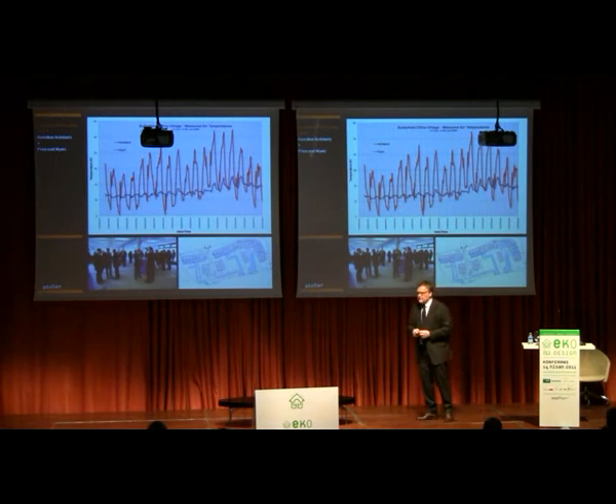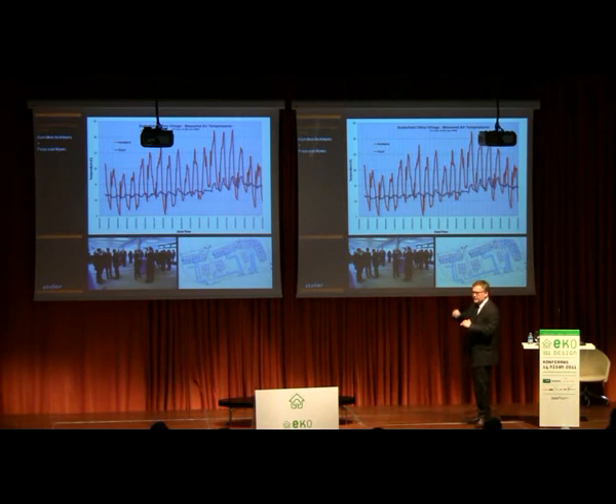In terms of thermal capacity, what we're looking to do is attenuate these swings in temperature. This is an actual reading from the building management system showing the outside temperature and the air coming off the earth pipe. On a day when England had three consecutive days at 32 degrees centigrade, which doesn't happen often, the earth duct was still supplying air at 17 degrees centigrade, cool enough through the floor to keep the space comfortable.